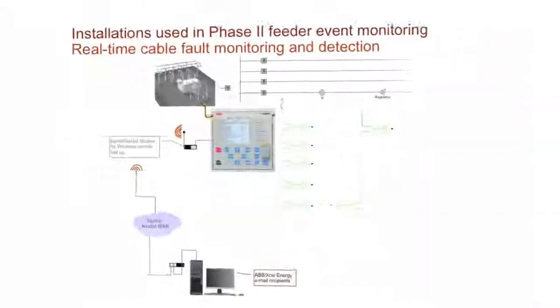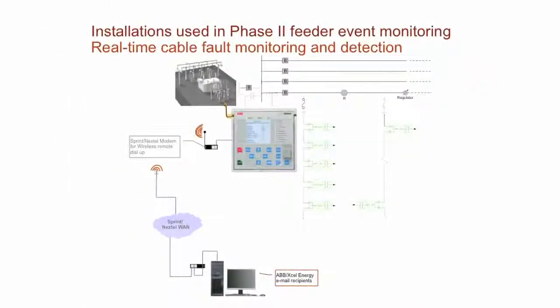Now, what protection and control relay would you put that in? If you're monitoring a feeder for feeder events, what kind of relay would you use? A feeder protection relay, right. Because it's uniquely different and has its own algorithm running, you don't have to use conventional overcurrent functions, which in many cases can't detect these short-lived instances. You get the value add - it's the optimal cost-effective solution because it protects your main feeder, with all the voltage and current protection for standard feeder protection and control, plus the additional benefit of cable fault detection.